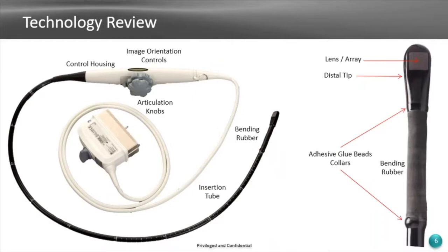Technology overview: on the outside of the probe, we have our control housing. This control housing is not submergible, unlike an endoscope where the control housing is IPX rated for submersion. These control housings are not, and we get a lot of transducers in where these control housings have been submerged in a cleaner or disinfectant, which can catastrophically damage these things.